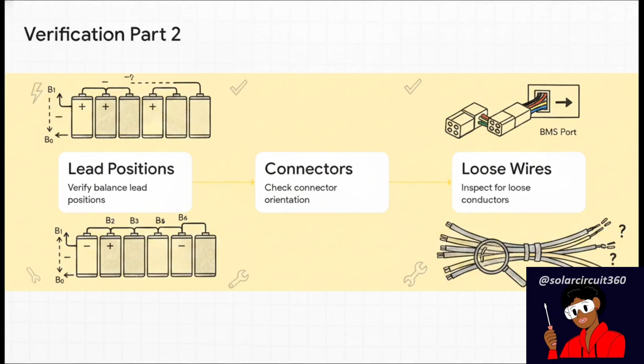Continuing down the checklist, step 5 is verifying those cumulative balance lead positions. Measure from B0 to B1, then from B0 to B2, making sure the voltage steps up predictably every single time. Next, check your connector orientation to make sure it matches your BMS port perfectly. And finally, inspect the entire harness for any loose conductors that could cause intermittent false readings down the line. Only after all of these measurements perfectly match your expectations should you finally connect that BMS.